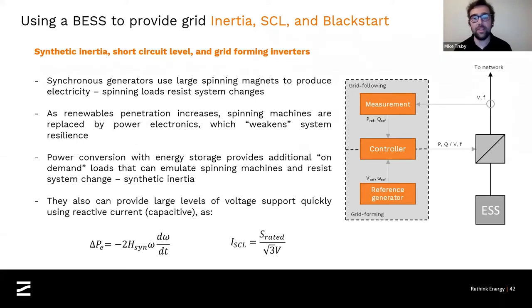The other thing that batteries can do is provide short circuit level. In a fault event, all of the current in your system rushes to the fault. As a result, much like with the reactive power service we talked about before, your voltage starts to change, and specifically it starts to collapse. All of your energy is leaving your system through this fault, so your voltage goes down. What batteries can do very quickly is inject very large amounts of reactive power to prop up that voltage. It's almost a natural response of the inverters. They will inject these large reactive, capacitive currents into the network, and that will prevent voltage collapse and allow the protection systems time to isolate the fault and protect the rest of the network and prevent a brownout or a blackout around it.